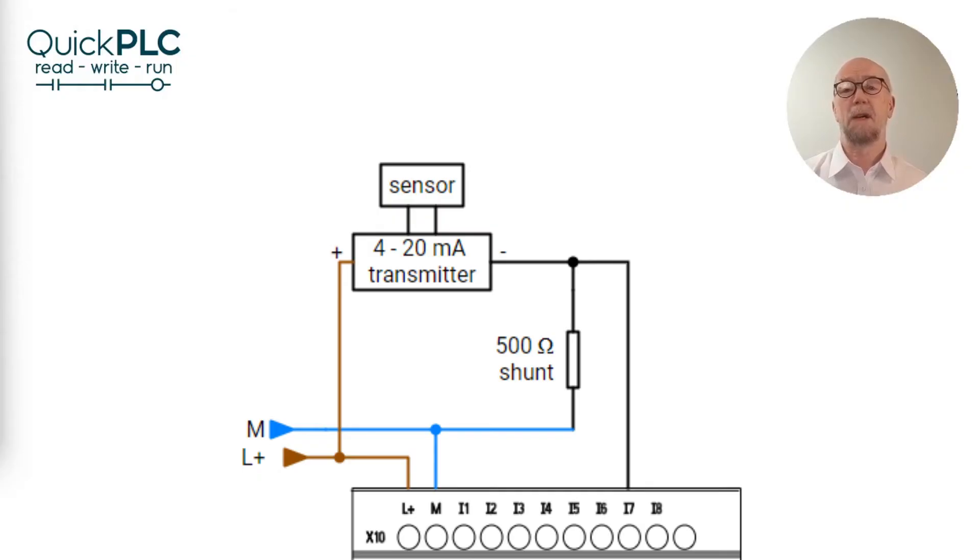Be aware that a loop powered transmitter requires a minimum voltage across its two terminals for it to operate correctly. At 20 milliamps we're going to drop 10 volts on the 500 ohm shunt leaving only 14 volt for the sensor on a 24 volt power supply. This should be fine for most sensors but if you need a few more volts then consider using a 250 ohm shunt if you can tolerate the loss of resolution with a 1 to 5 volt input rather than 2 to 10 volt.